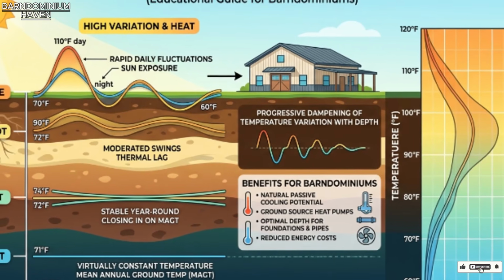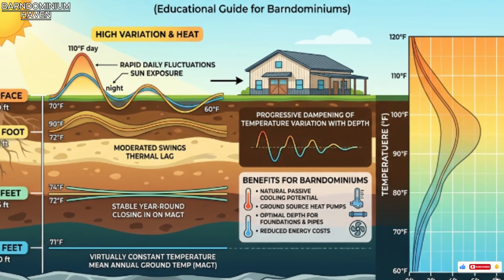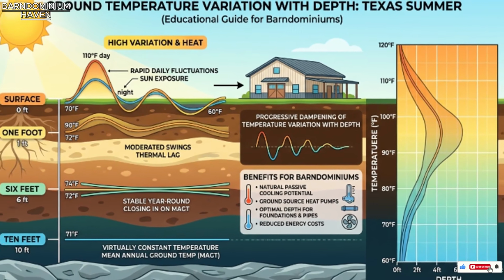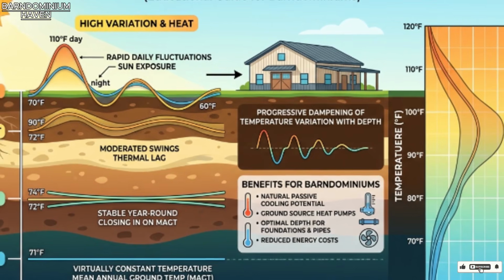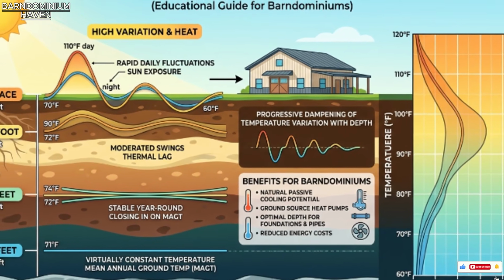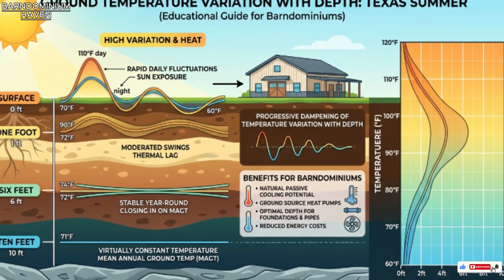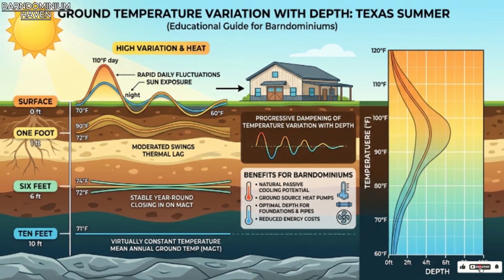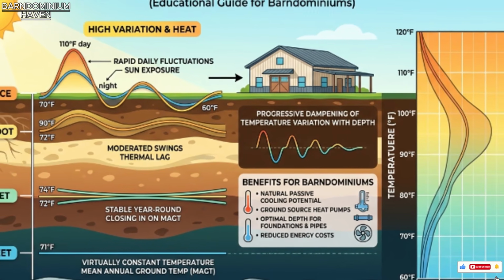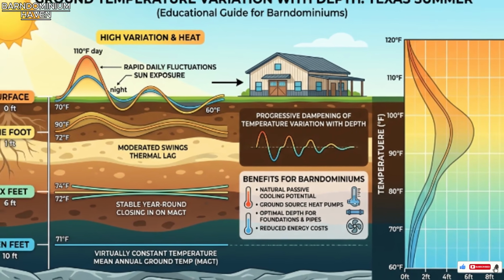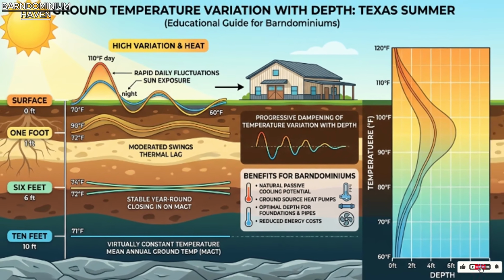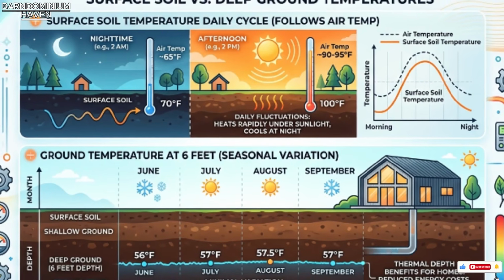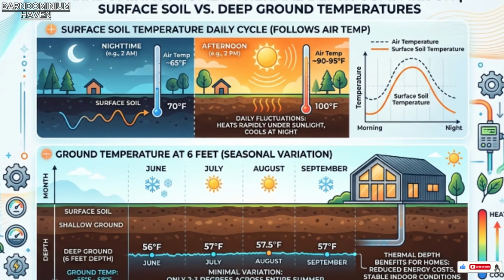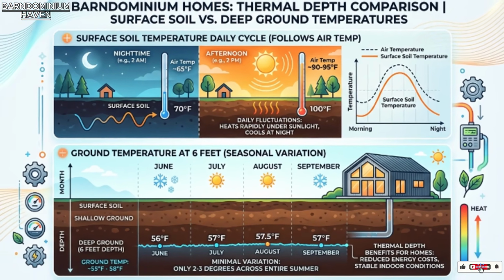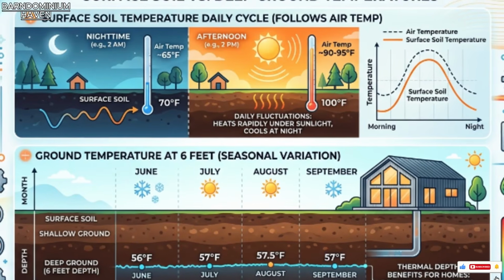The ground's thermal stability at depth, its ability to maintain a consistent temperature regardless of surface conditions, is a consequence of the Earth's thermal mass and thermal diffusivity. Properties that determine how quickly temperature changes at the surface penetrate downward through the soil. At the surface, soil temperature follows air temperature closely, cycling daily and seasonally with the ambient condition. At 1 foot of depth, the daily cycle is dampened.